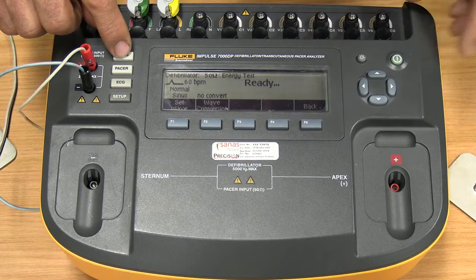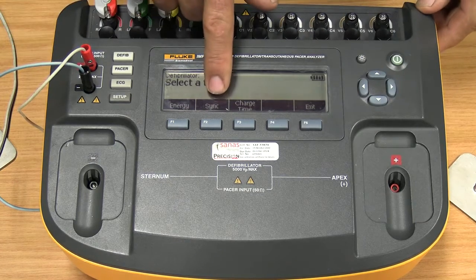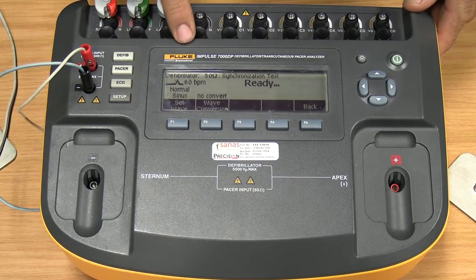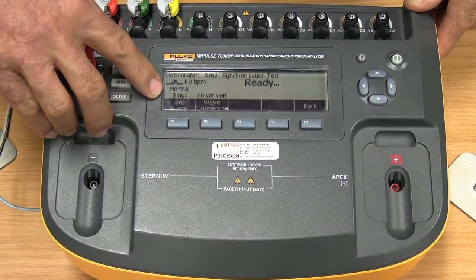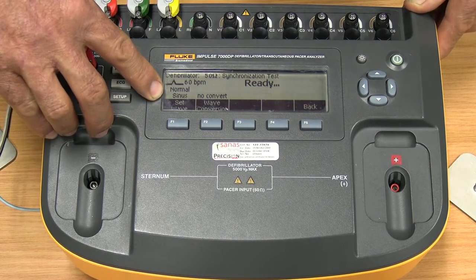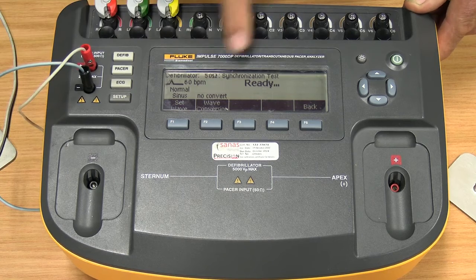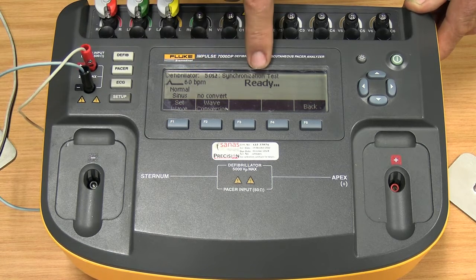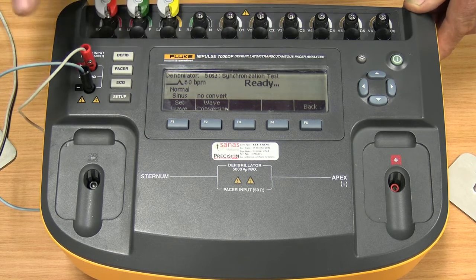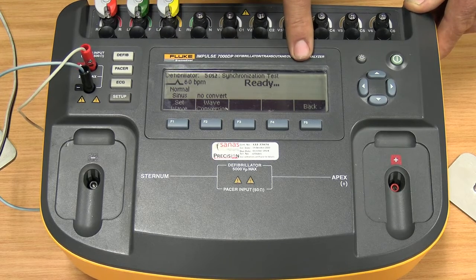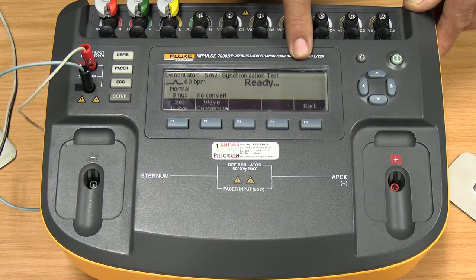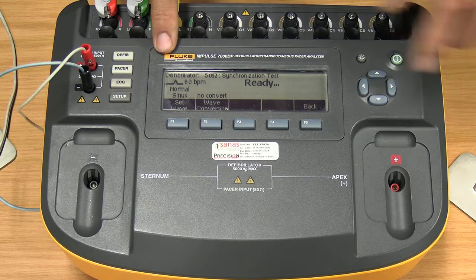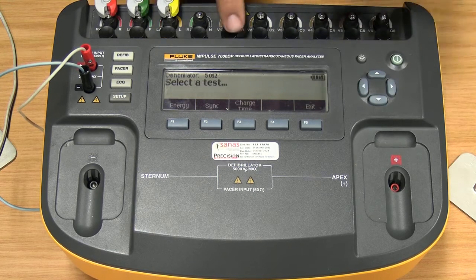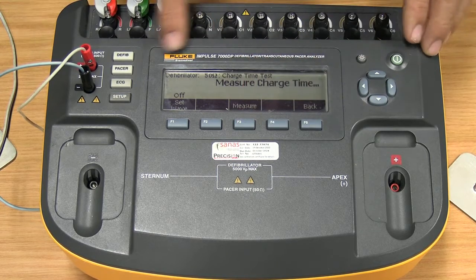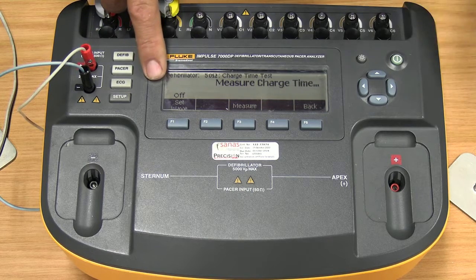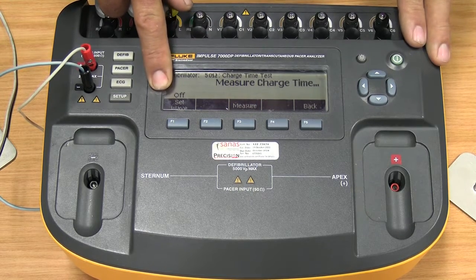Let's go back to defib again. Sync time. If I go to sync time, again, I choose the waveform which I want to use to synchronize from, and the same as the conversion time. When the machine is ready, you can apply the shock, and the unit will measure how long after the R wave the machine delivered the shock. If we go back, the next one is charge time. Charge time you don't really need a waveform for, but the function is there to set a waveform.